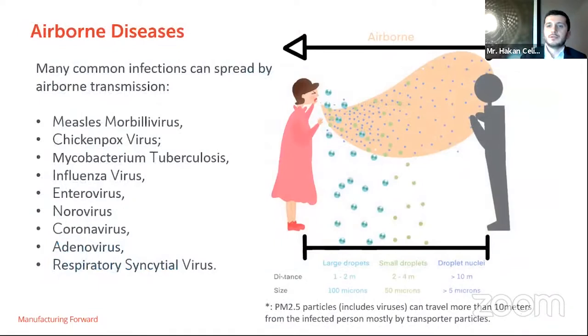Also related to particle pollution, microorganisms can be spread in aerosols, dust or liquids. Such infected aerosols may stay held in the airflows long enough to travel considerable distances, very long distances. As an example, a sneeze can easily transfer infectious droplets the full length of the aisle. There is a visual on the right side, which is based on the CFD analysis of the sneeze. As you can see, particles generated by a sneeze can travel more than 10 meters easily.